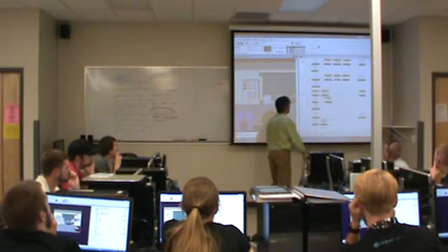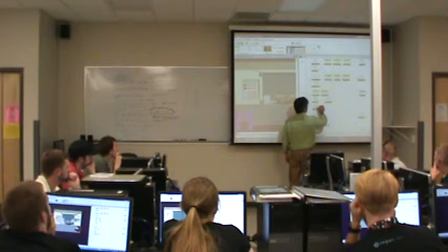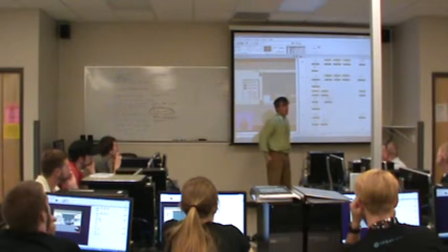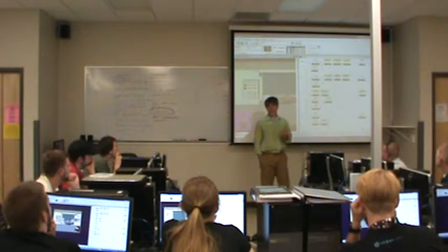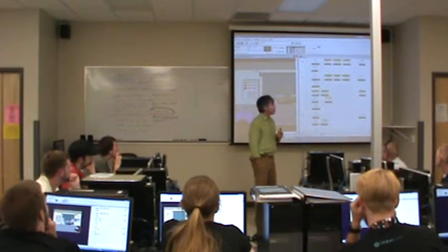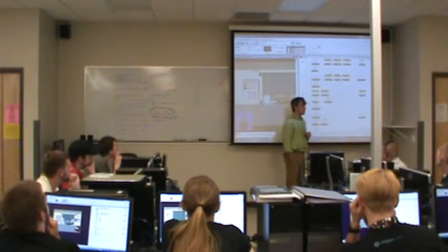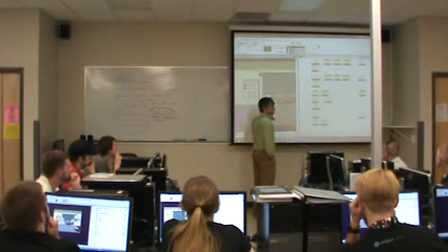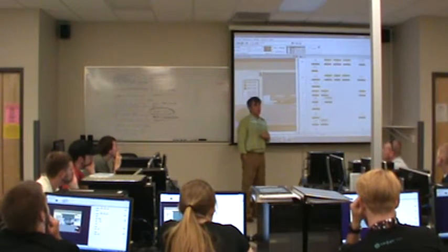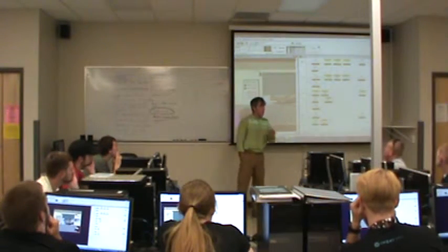There's another set of conditions for the light being on solid. We're missing those conditions because we've changed the definition of how we want the system to work. What are the conditions for the lamp being on solid? Not only does the door have to be between the limit switches, but something else has to be true. The motor should not be moving.